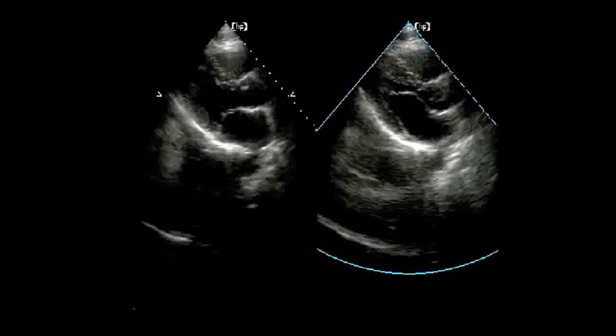All right, now there are four user-adjustable controls that change the frame rates, and we have to know about them. They're going to be especially important when we do color, so this has two purposes. The first control is depth of view. Shallow imaging looks like this, and deep imaging looks like this. Well, which image is made quicker? The shallow image. So shallow imaging means I make a frame quicker, my frame rate's higher.